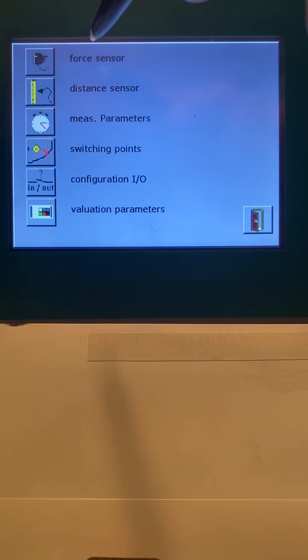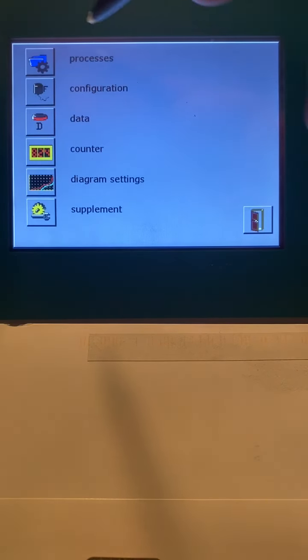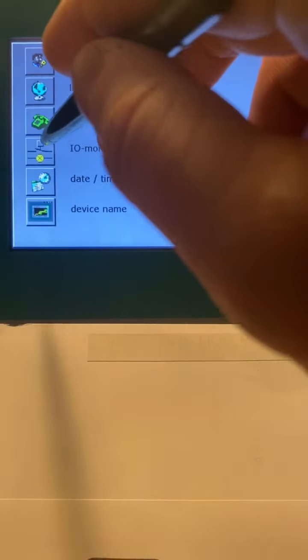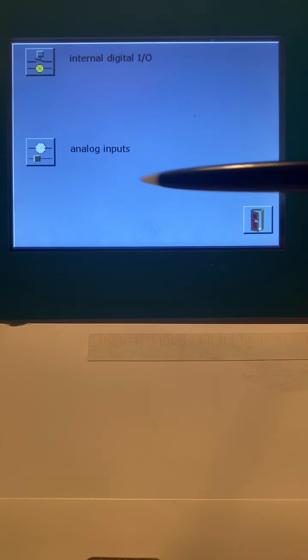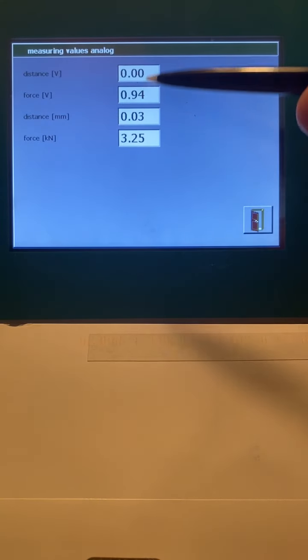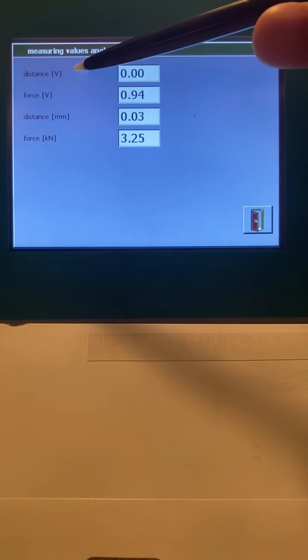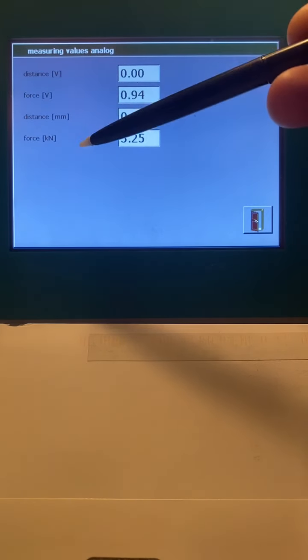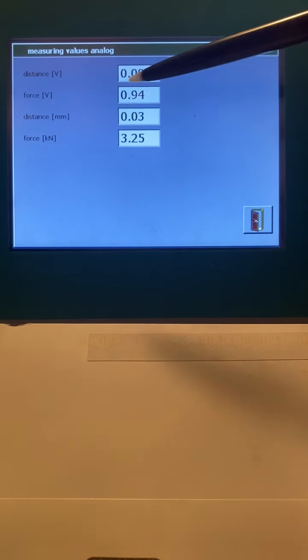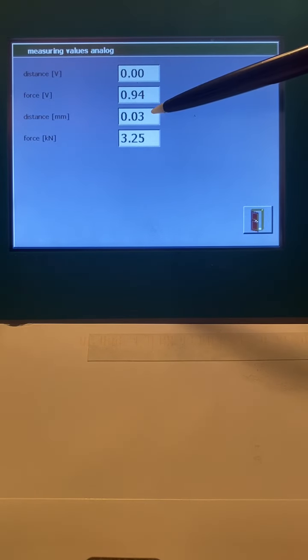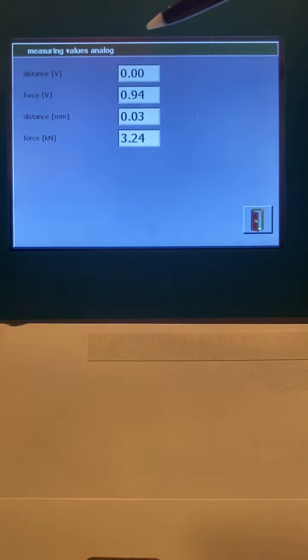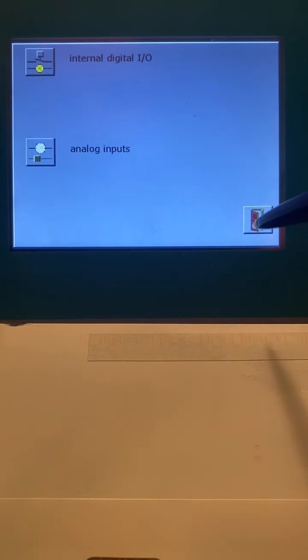And then the other thing I want to do is I'm going to go back to my menu. Once I've set up my sensors, I can go to supplement and I can go to IO monitor. And under supplement and IO monitor, I can physically see the sensors. So here's showing me the voltages of the distance and the force, and this is the actual scaled values. So I've got 0 voltage and 0 distance. When I drive the press up and down, you're going to be able to see those numbers. This is how you would verify that those sensors are working.